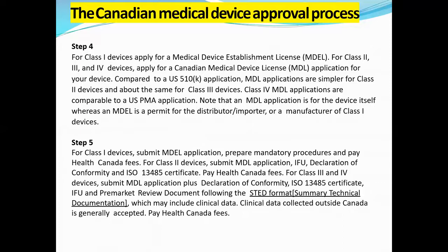Then, for a class 1 device, apply for a medical device establishment license, that is MDEL. For class 2, 3 and 4 devices, apply for a Canadian medical device license, that is MDL. So MDEL is the Medical Device Establishment License, and MDL is the Canadian Medical Device License. These are the two applications for different classes of medical device. Compared to the US 510(k) application, MDL applications are simpler for class 2 devices and about the same for class 3 devices. Class 4 MDL applications are comparable to the US PMA application, the pre-market approval application. Note that an MDL application is for the device itself, whereas an MDEL is a permit for the distributor and importer or the manufacturer of a class 1 device.